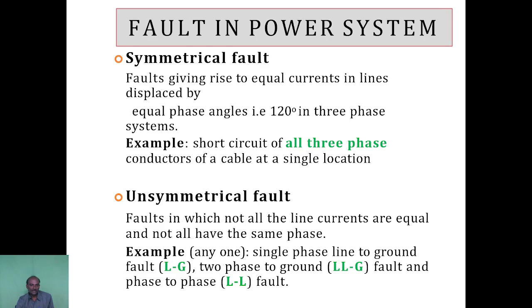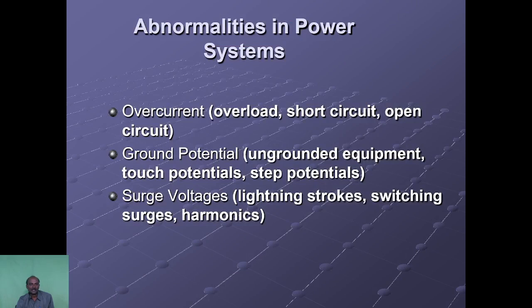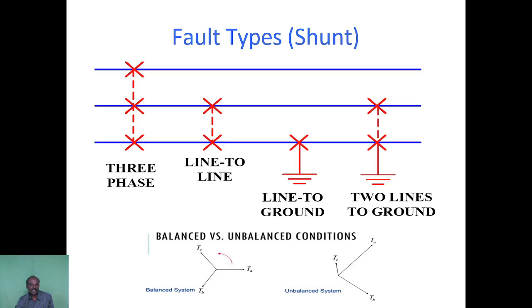So unsymmetrical faults. Here the line currents are not equal. The fault currents are not equal in all the phases. The faults are categorized as single line to ground fault, double line to ground fault, or line to line fault. So various abnormalities in the power systems are due to the faults, which are creating the disturbances in the system.